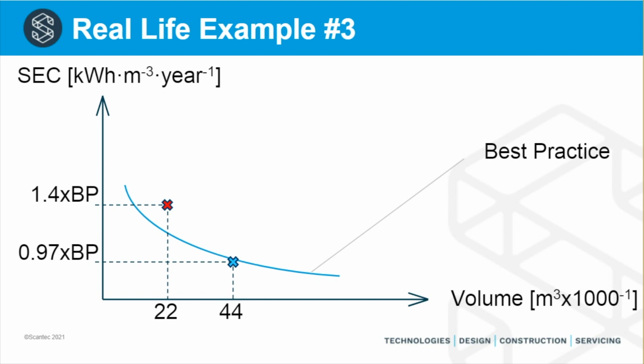This gentleman disposed of that plant and bought a new plant with a refrigerated volume of 44,000 cubic meters. That's the blue cross there. And that new plant, which, as I said before, is conceptually identical to the old plant, uses 0.97 times best practice. The only difference between the two plants is that the old plant was liquid overfeed and the new plant is dry expansion. So the effect we see there is a 1.3 times reduction in SEC value, and that is caused by the elimination of heavy liquid in the suction line network of the plant.